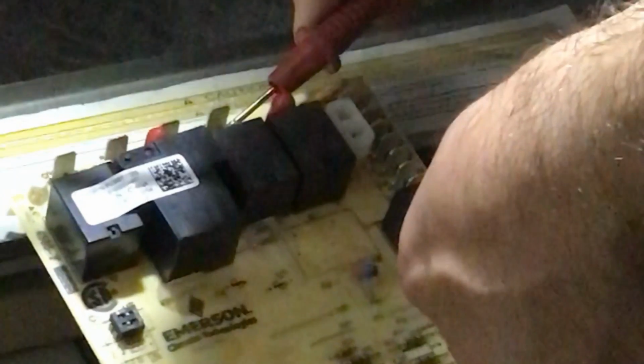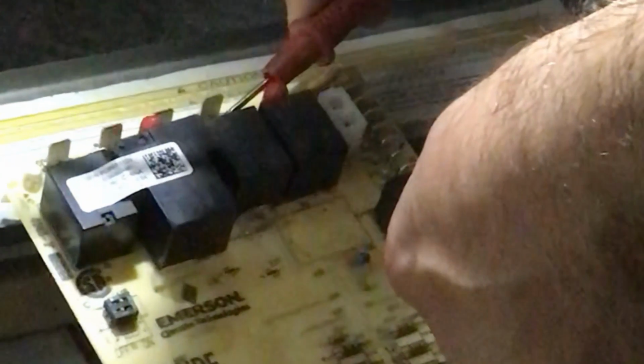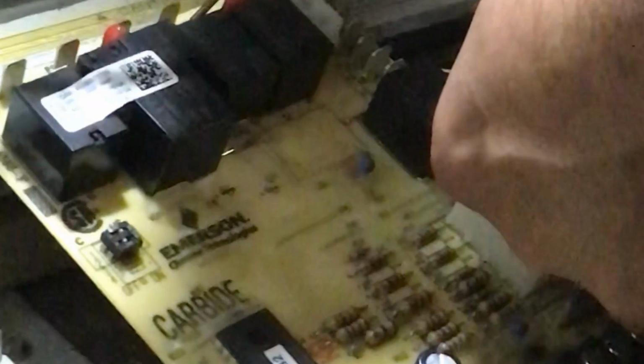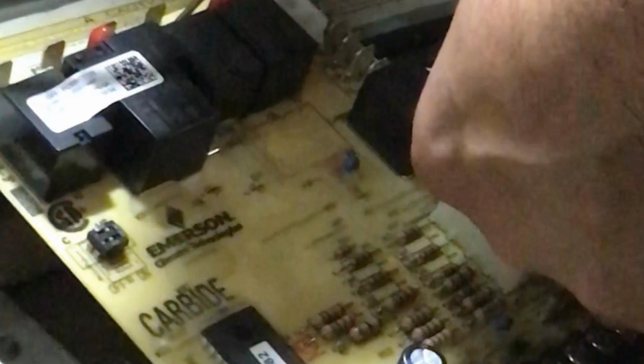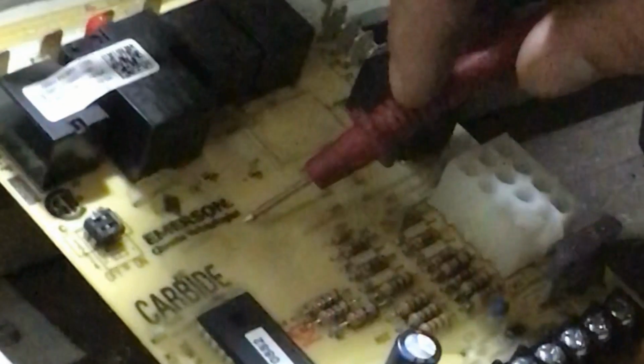Okay, so we've performed the tests. One lead to a neutral or a known ground, your other lead to your 120 volt output to your transformer. And like we said earlier, if 120 volts is coming out of this board to the transformer and you're not getting 24 out of the transformer itself, the transformer is bad. Now, if it's the other way around, everything's energized and powered up, and you perform this test and you're not getting 120 volts out of the circuit board, then your circuit board is bad. And so you would want to change that out.